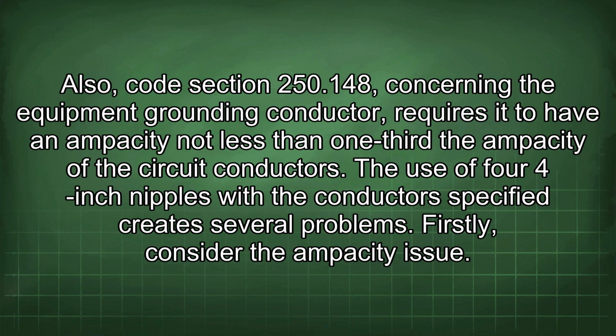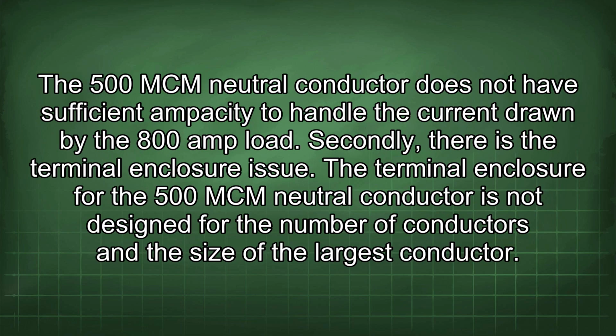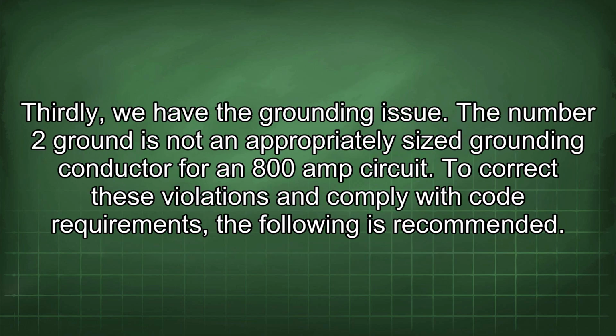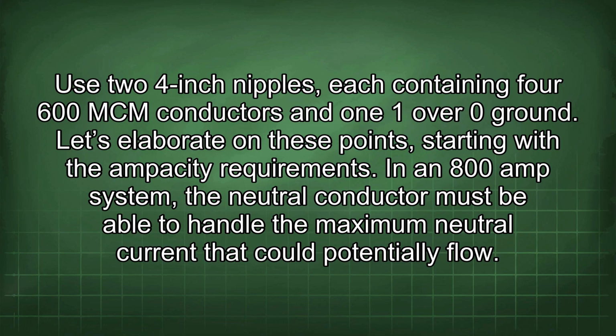Firstly, consider the ampacity issue. The 500 MCM neutral conductor does not have sufficient ampacity to handle the current drawn by the 800 amp load. Secondly, there is the terminal enclosure issue. The terminal enclosure for the 500 MCM neutral conductor is not designed for the number of conductors and the size of the largest conductor. Thirdly, we have the grounding issue. The number 2 ground is not an appropriately sized grounding conductor for an 800 amp circuit. To correct these violations and comply with code requirements, the following is recommended. Use 2 4-inch nipples, each containing 4 600 MCM conductors and 1 1/0 ground.